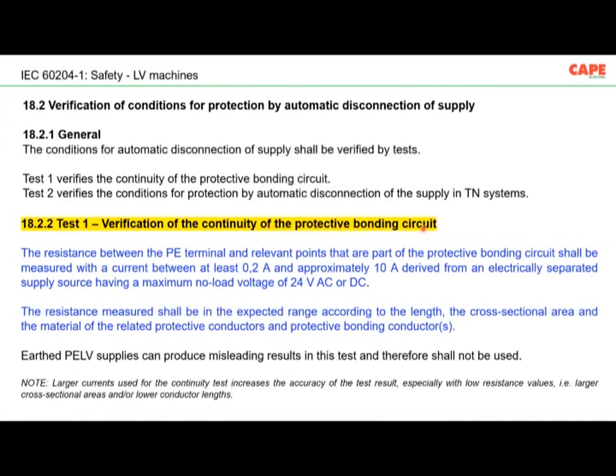Verification of continuity of the protective bonding circuit. The resistance between PE terminals. So where do you have the PE terminal? The PE terminal is in the machine. The resistance between the PE terminal and the relevant points that are part of the protective bonding circuit shall be measured with a current between at least 0.2 ampere and approximately 10 ampere, derived from an electrically separated supply source. So basically, after making the connection, you are supposed to test the resistance of that particular connection with a meter having an electrically isolated supply, with a test current of about 10 ampere. I would recommend that if you go for an Indian meter, you should have a test current of minimum 10 ampere. Otherwise, you will not get the correct value.